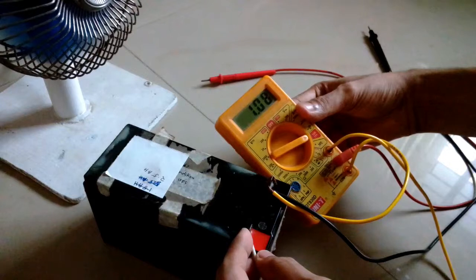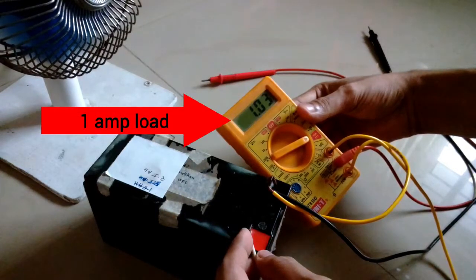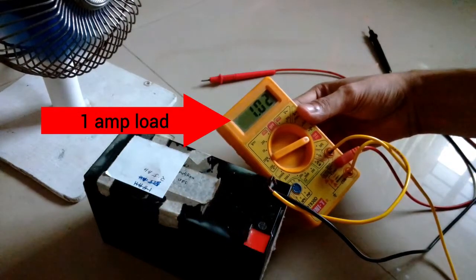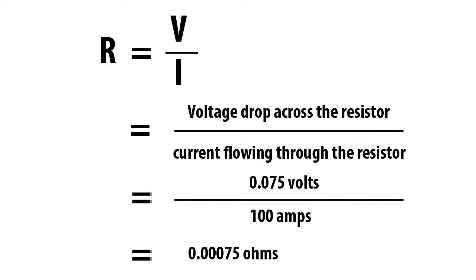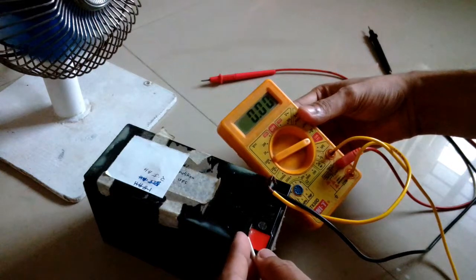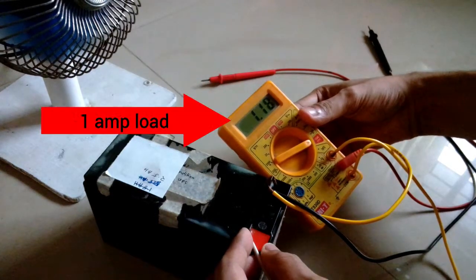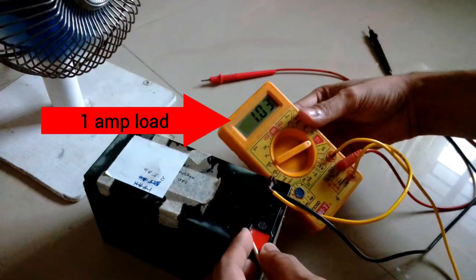For example, if a shunt resistor is rated for 100 amps and 75 millivolts, then according to Ohm's law, resistance equals voltage drop across the resistor divided by the current flowing through it: 0.075 volts divided by 100 amps equals 0.00075 ohms. So it's clear that we can't measure in milliohms or microohms with our multimeters.